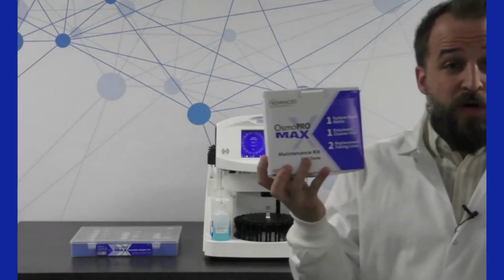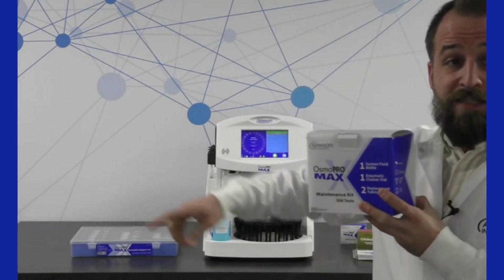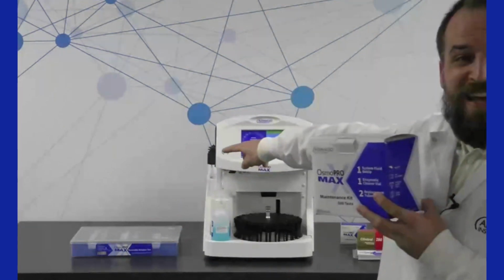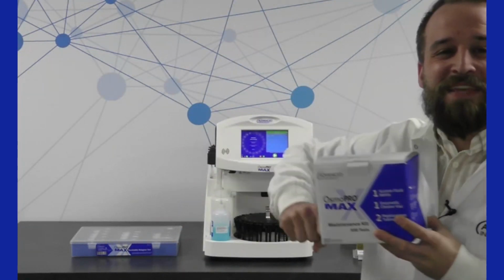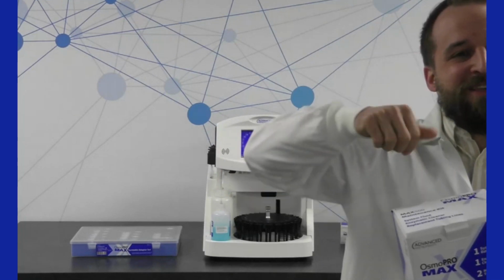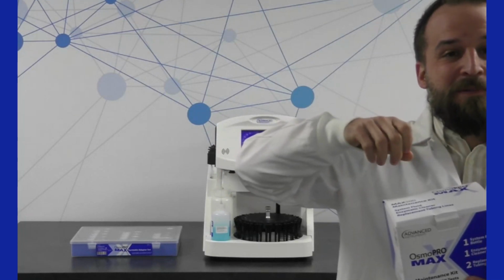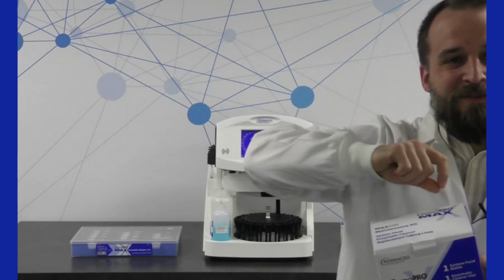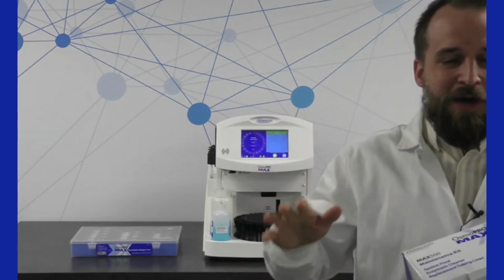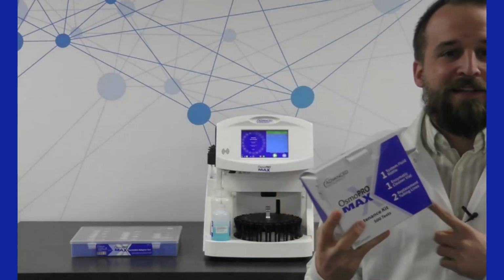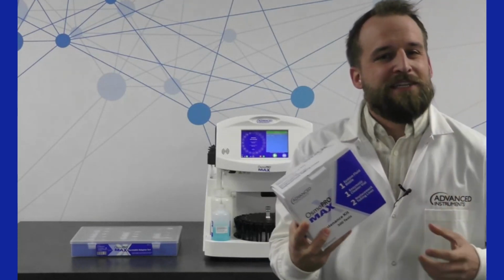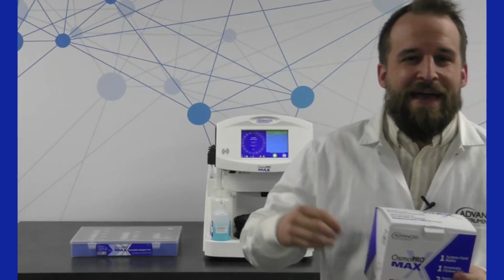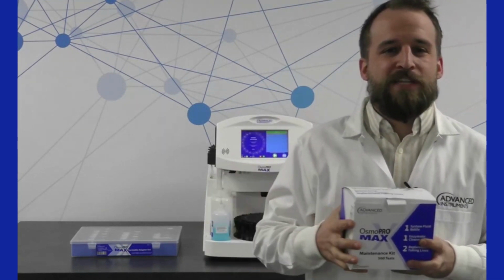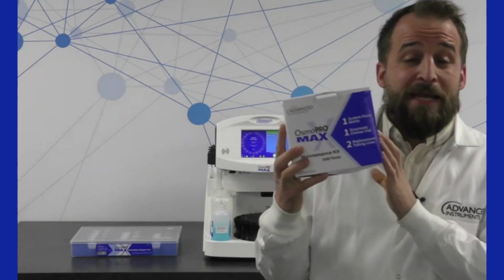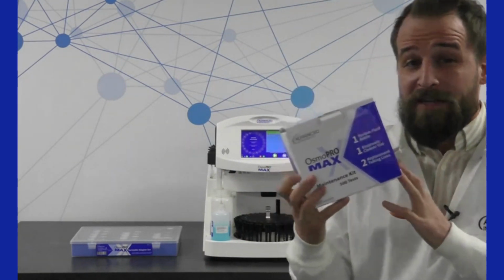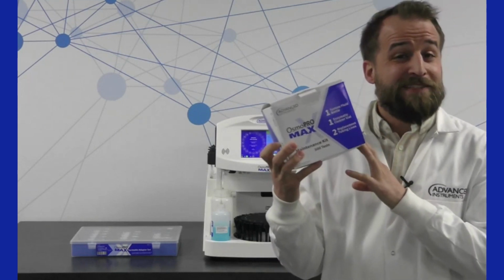You're going to get 2 of those peristaltic tubes to change in that black colored housing on the side of the instrument. It's really easy. They clip right off. You lefty-loosey the coupling right off the side of the instrument and righty-tighty everything right back on, put the housing back on, and you're good to go. And then it comes with a tube of enzymatic cleaner as well, which is just a pepsin-based cleaner that ensures that the fluidic pathway is cleansed at the end of each day, but also as part of the maintenance kit. This is called the Max 500 kit because it's required every 500 tests.